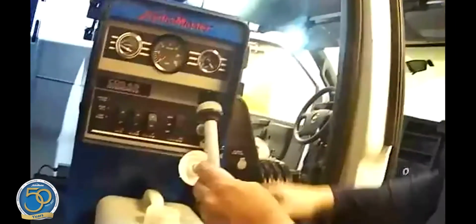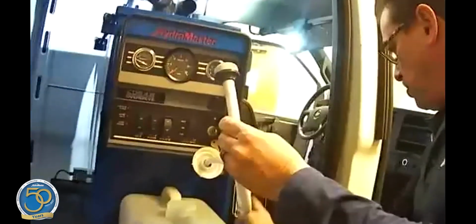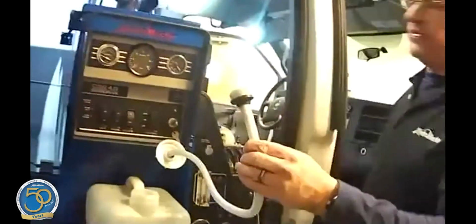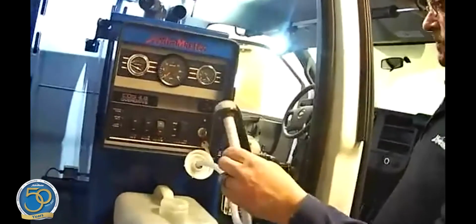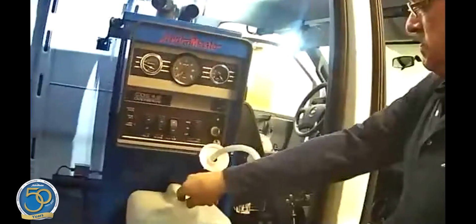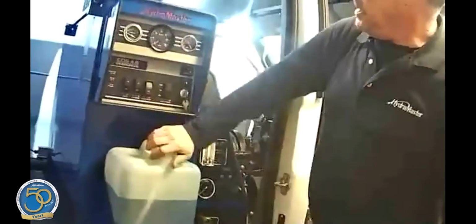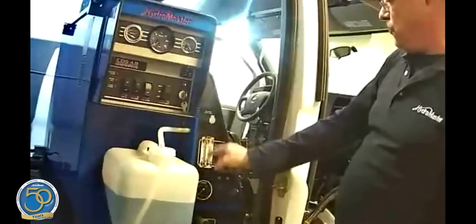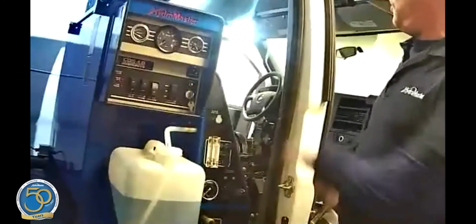When you turn it to prime, it sucks all the solution out of the system and dumps it into the recovery tank. It just blows out the system and sucks it all out, essentially evacuating it. Evacuate all the liquid until you see no more moisture coming through your flow meter, and you'll have that whole system evacuated.